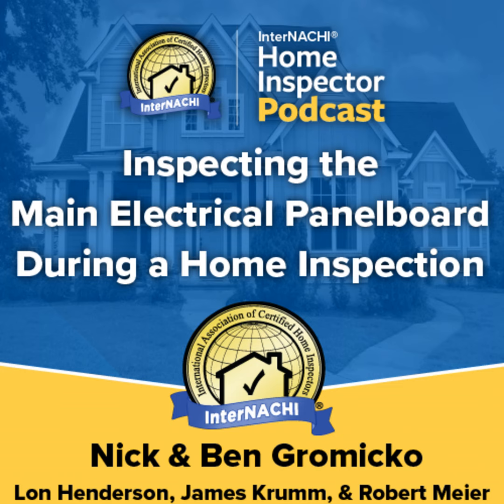Type SE, style SEU service entrance cable is primarily used to convey power from the service drop to the meter base and from the meter base to the distribution panel board when the main disconnect is installed at the main panel board. SEU is an unarmored service electrical 3-wire cable with 2 conductors and a neutral. SEU typically has an oval shape because the stranded neutral conductor wraps around the cable to create an oval shape. SEU cable has a neutral conductor but does not have a grounding conductor.